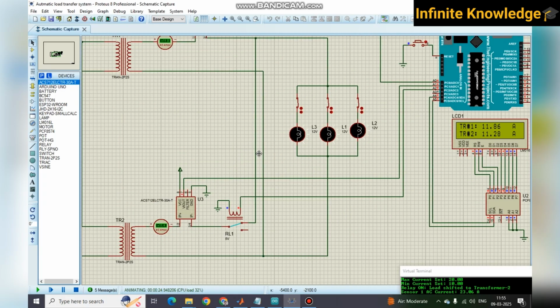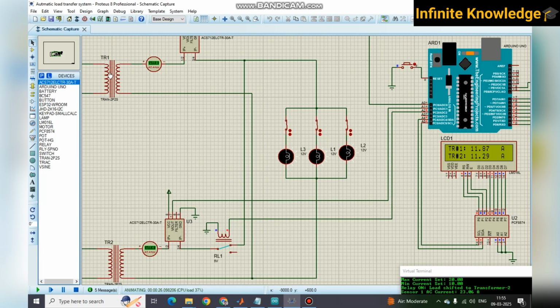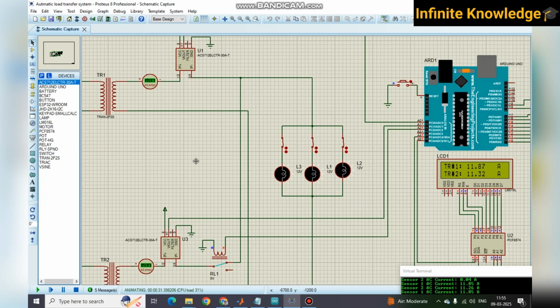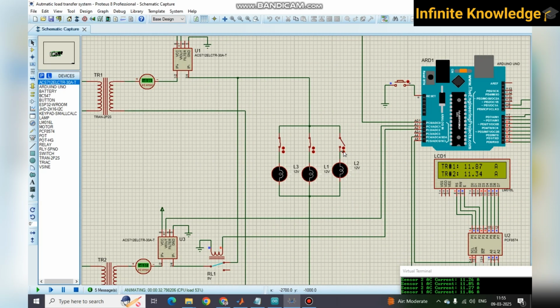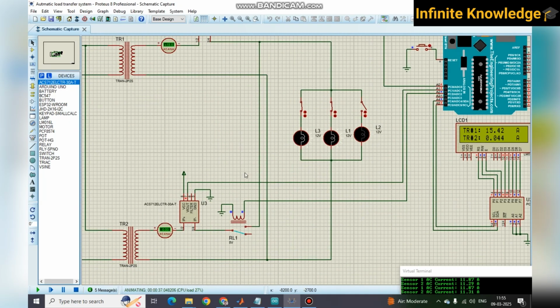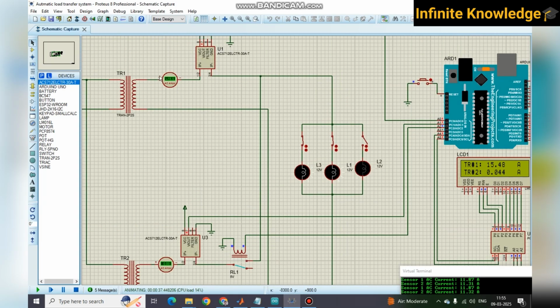Now everything is okay, because TR1 was previously overloaded with 23 ampere, but when TR2 came into the picture, load sharing reduced the secondary ampere on TR1. Previously it was 23 ampere, right now it is only 11 ampere. So what if the ampere now goes below 10 ampere? If I isolate one of these lamps or loads, you can see the load decreases, and on both transformers it is 7, which is less than 10 ampere. At that time TR2 is automatically isolated and only TR1 remains in the picture.